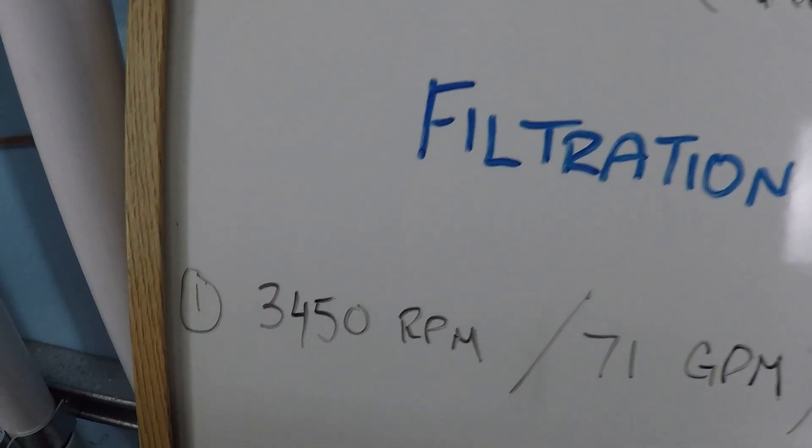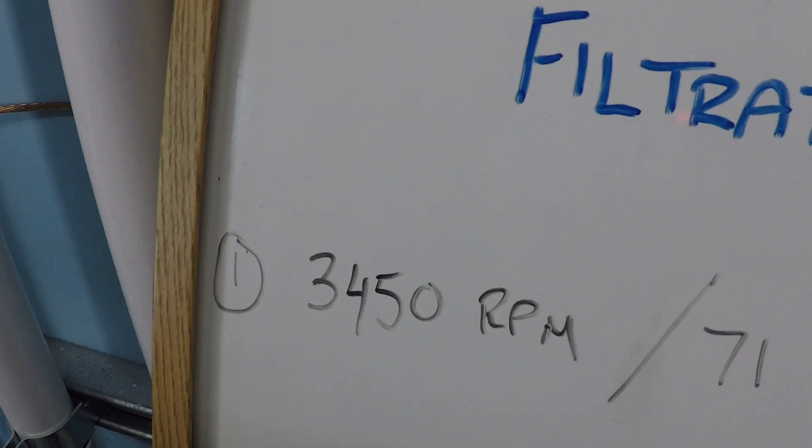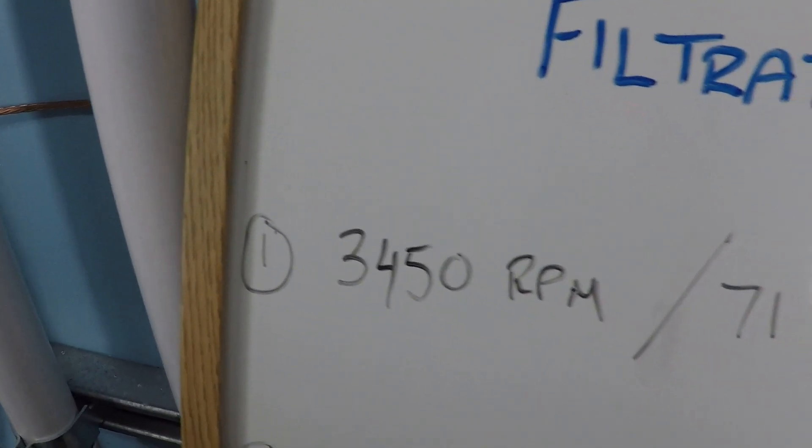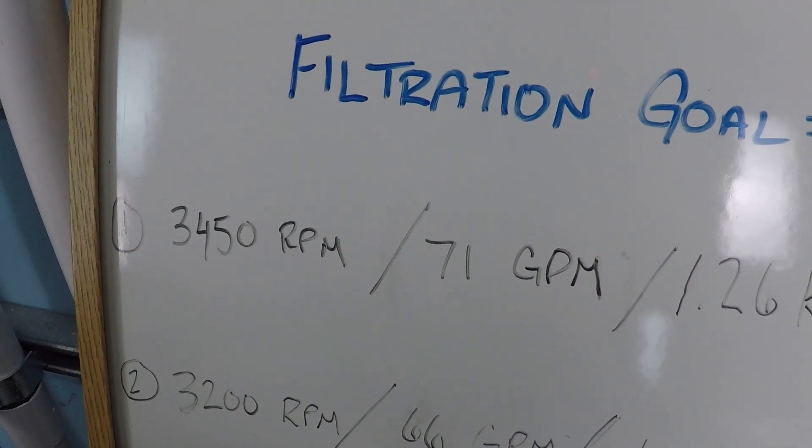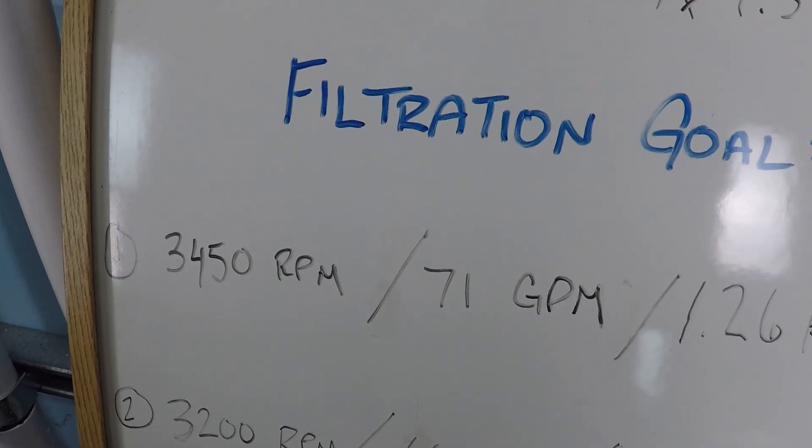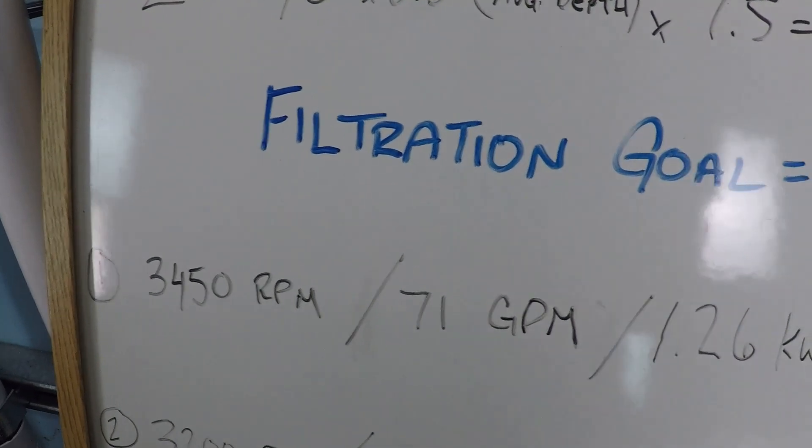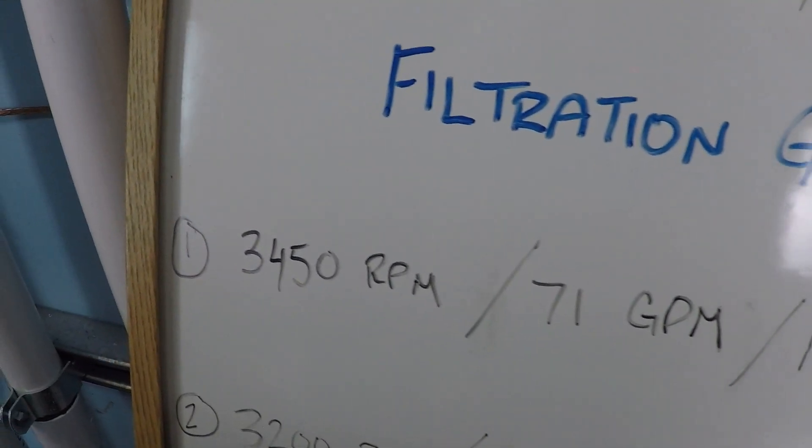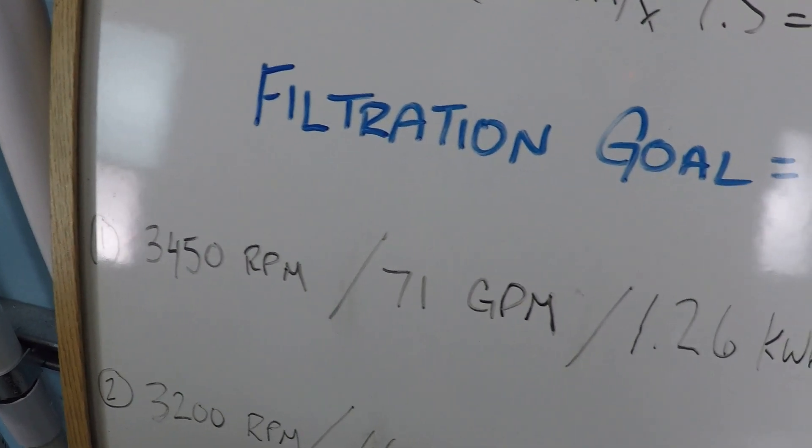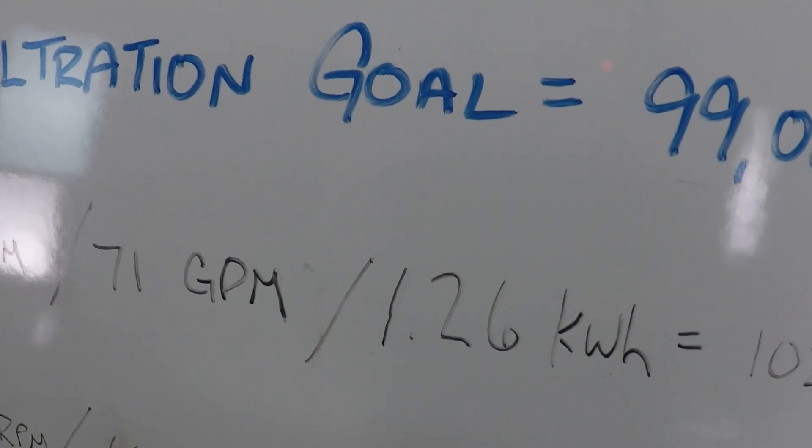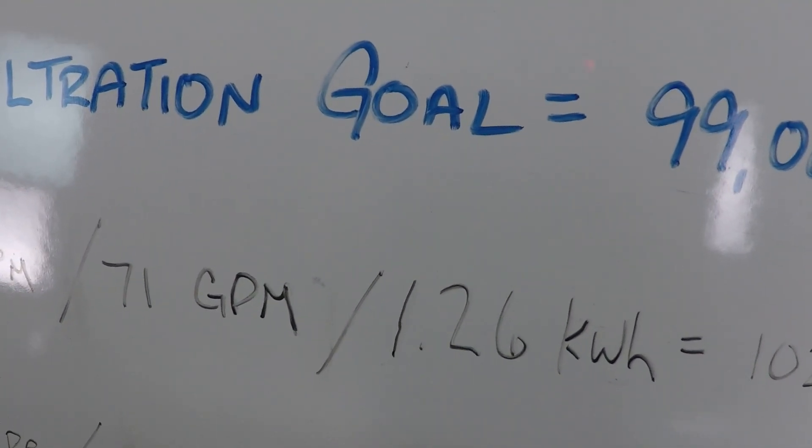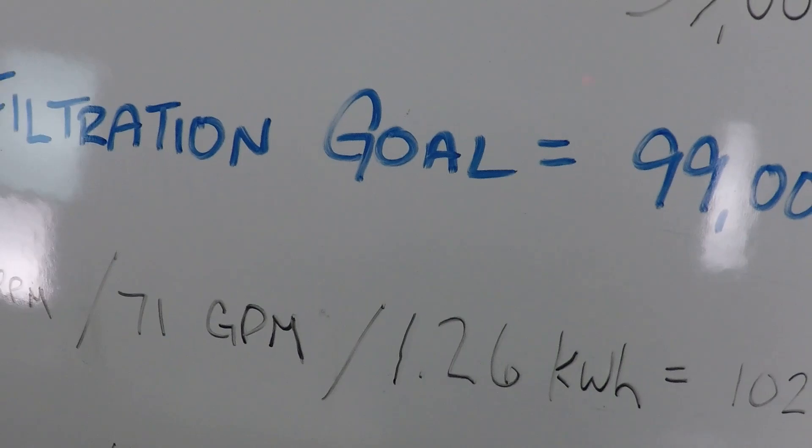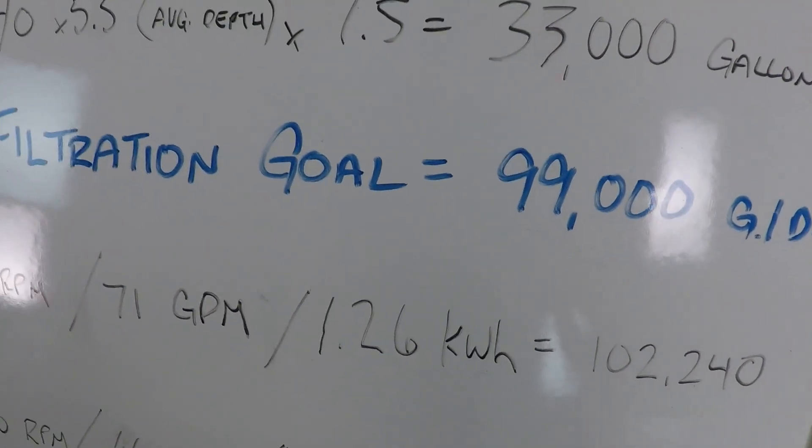So let's say you had a 3,450 RPM pump. If you only have a single speed pump, that's the RPM that you have. And on this system, which is a very basic system with approximately 30 feet of head resistance, we're able to achieve 71 gallons per minute when the pump is operating at maximum speed, this one and a half horsepower pump. During that time, we're consuming 1.26 kilowatts of power, 1,260 watts of power consumed every hour that the pump is operating like this.